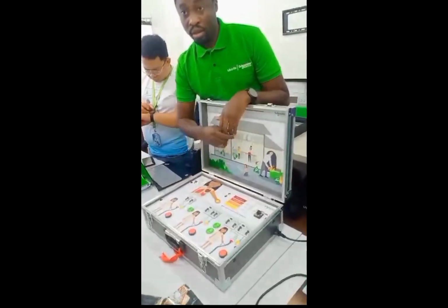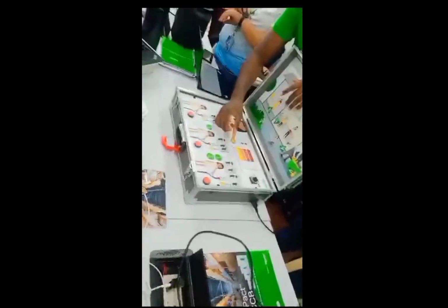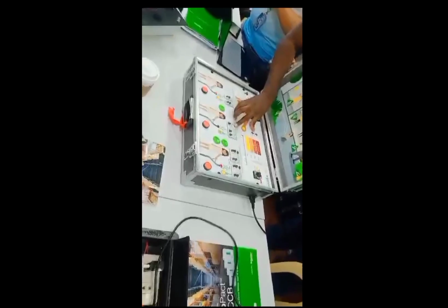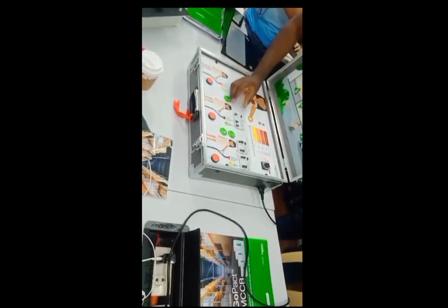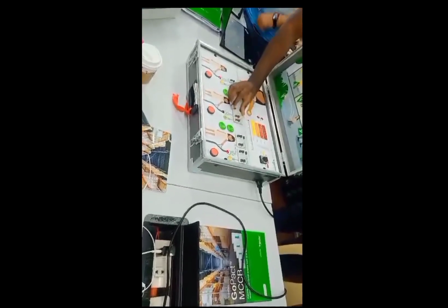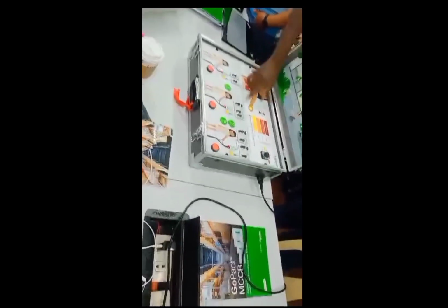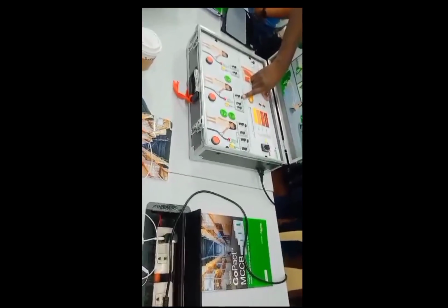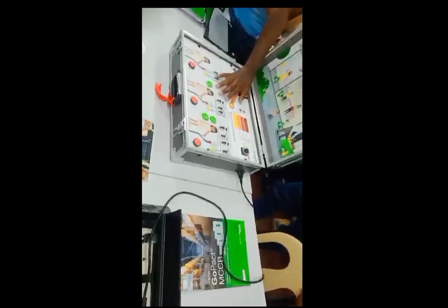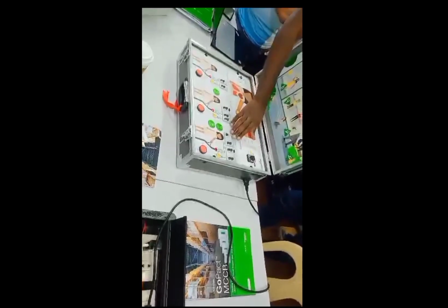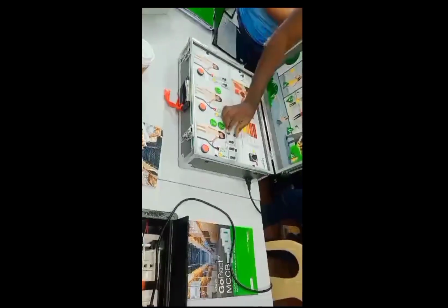So how the testing is done is you switch off all the loads, and then you just come and press on it. So if it trips, you've confirmed it's still operational, it's still functional, you're fine. You put back the loads on. Even your GFCI socket outlet must have this test button. It's a requirement. And when you have it at home, you should probably be testing it every now and then, just to make sure that it's still operational. Okay. So that's it for this panel.